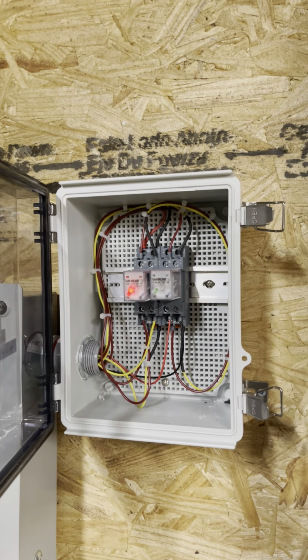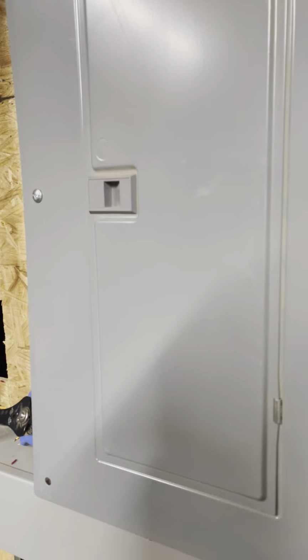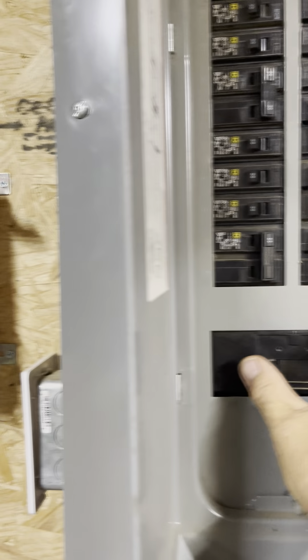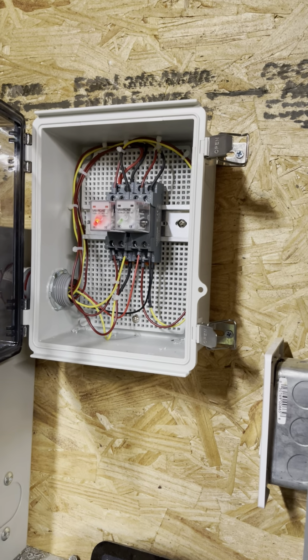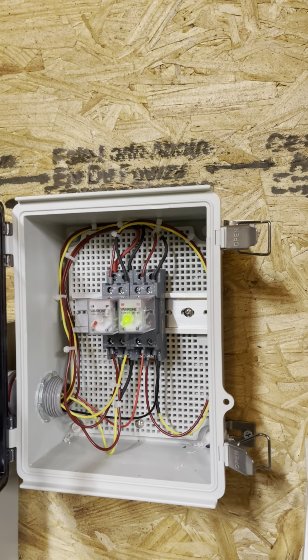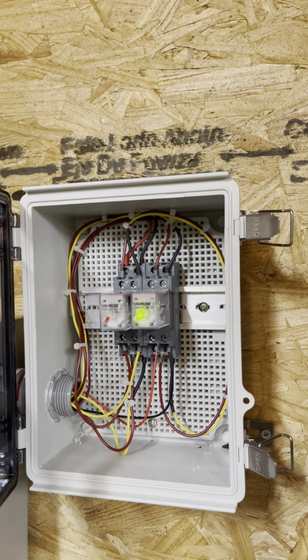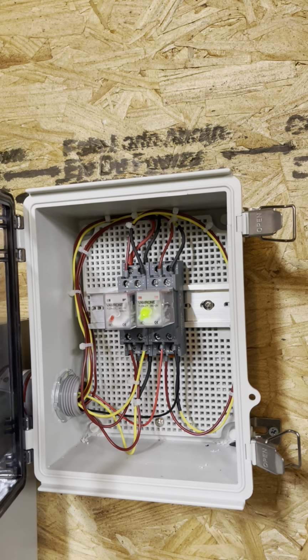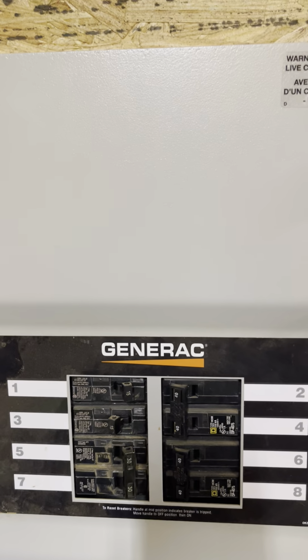And if the... I don't have a demand on the batteries right now, so I'm going to shut some of my batteries down, see if I can create a demand. And I'm going to shut my main grid power off and pretend like there is a power failure. And instantly it switches over and says, oh, I need to charge my batteries. The green LED comes on. I don't know if you can hear that. The generator just fired up.